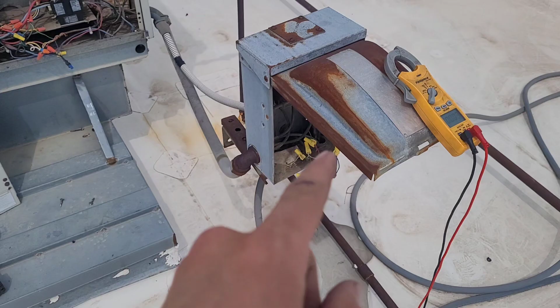So we're getting voltage into this system from something else. There's a random 2-wire down there. That's maybe what I'm suspecting, but still, it's really odd because are both of these units called by the same thermostat? It's very strange. Okay, so the random power is coming from this 2-wire, which we're gonna figure out where it goes. It was tied in from this red over to there and then to this red. Very strange. So the 2 wires that were feeding the voltage come all the way across the building over from these 2.